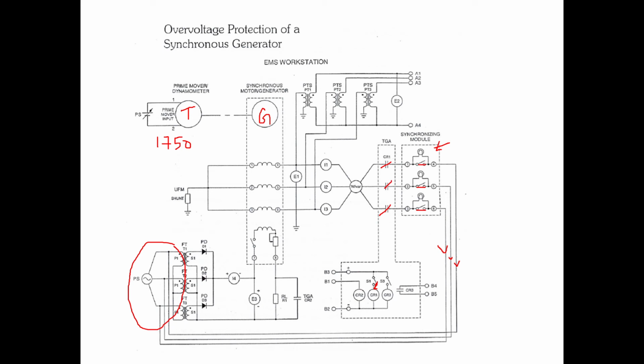Now the question is, how do we create the fault? Here we are going to create the fault by suddenly removing the load. That means we are going to disconnect the generator from the grid. How to do it? Manually open the switch S1. When you open the switch S1, what will happen? The CR1 contact will be open. When the CR1 contact is open, you are disconnecting the generator suddenly from the grid.